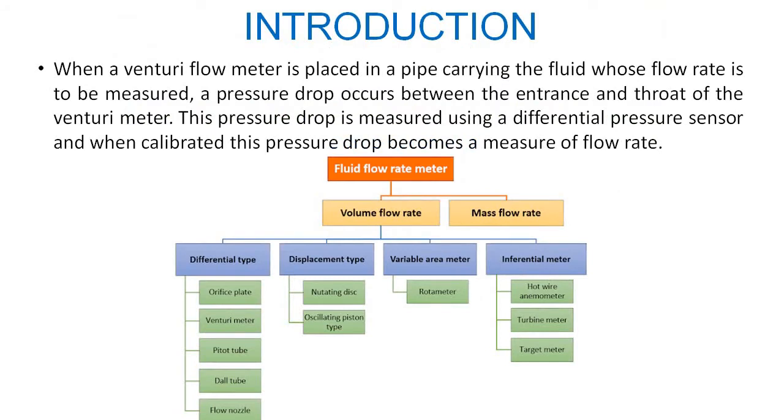First of all, introduction. When the Venturi flow meter is placed in a pipe carrying the fluid whose flow rate is to be measured, the pressure drop occurs between the entrance and the throat of the Venturi meter. Now this pressure drop is measured using a differential pressure sensor. And when it is calibrated, this pressure drop becomes the measurement of the flow rate.